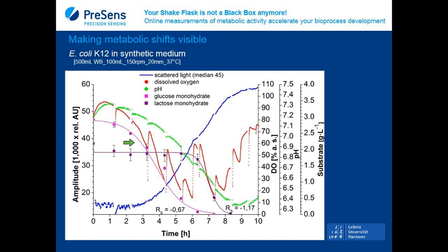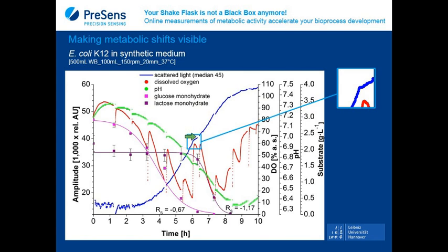Let's have a closer look at what's going on here. You see here that basically at this point glucose goes into limitation while oxygen concentration is increasing. And the pH stops to decrease. And also, looking at the scattered light at the same time, we see a little bend which indicates the slowdown or even growth stop during the shift. Because what happens here is this change. You see that after this depletion of glucose, the cultivation has to adapt to the metabolic change, and this is clearly indicated by our biomass sensor, also by the oxygen sensor. So even without having the glucose and lactose offline measurement, the metabolic shift is clearly shown with this example.